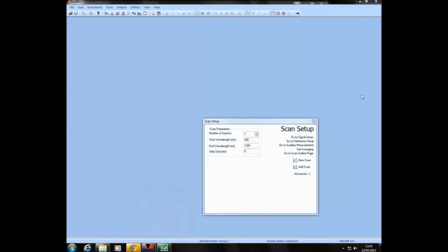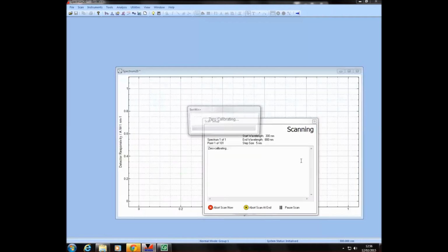the position. Whilst we have already calibrated the system over the range 300 to 1200 nanometers, in the specific case here of an amorphous silicon device, we need only measure up to around 800 nanometers, so we will change the end wavelength accordingly. Now, as opposed to the previous sample, a production grade monocrystalline silicon sample, the amorphous silicon sample here is of research grade, and one does question how the sample will deal with the one-sun bias. So in the first instance, I will perform a scan with no light bias applied to see what response we get.